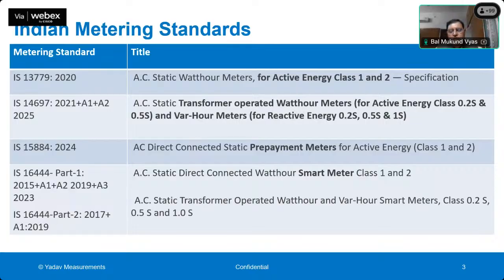There are two major differences between a smart meter and a normal meter. One, the smart meter has a two-way communication capability. Two-way communication capability means the meter can send data to the utility head-end system. Head-end system means a computerized system or a server which is in the IT department of the utility, the electricity supply authority. So the meter can send data to the server, and similarly the server can send commands to the meter. So this is two-way communication.